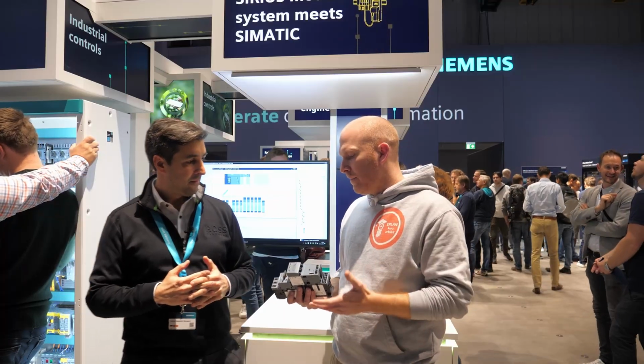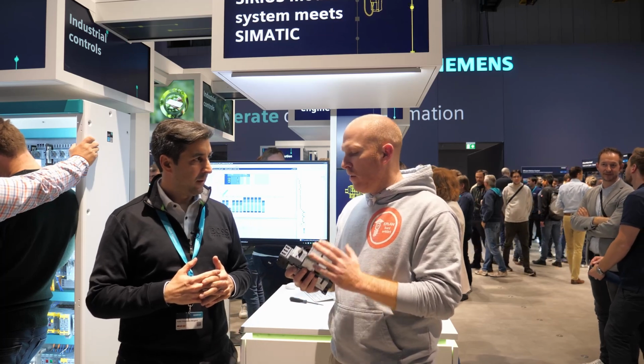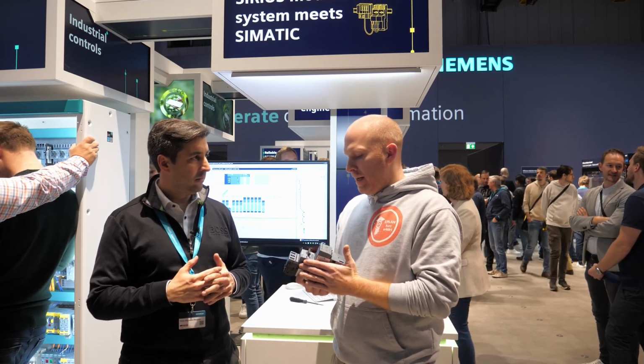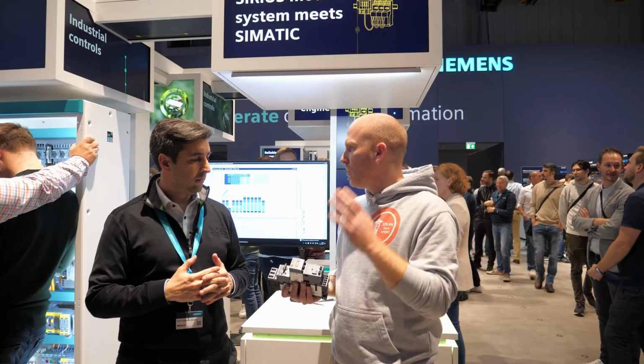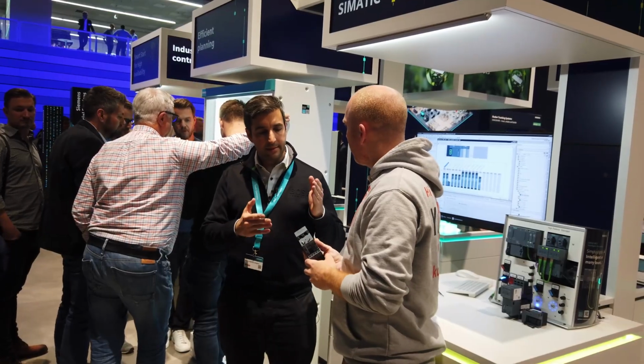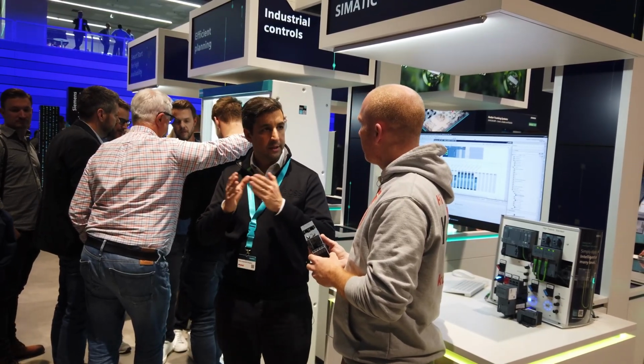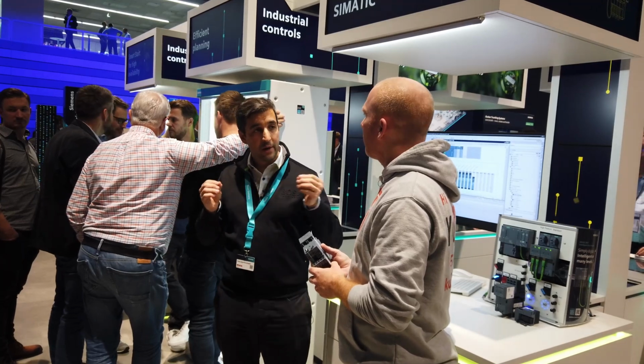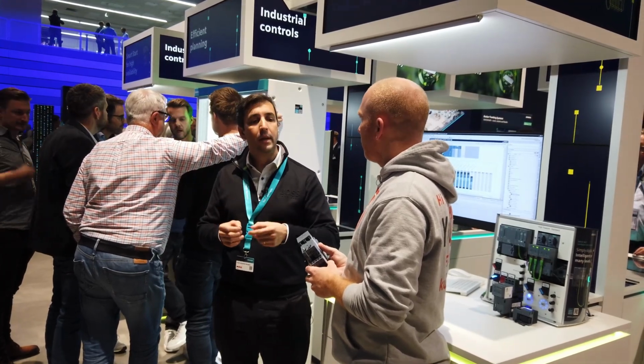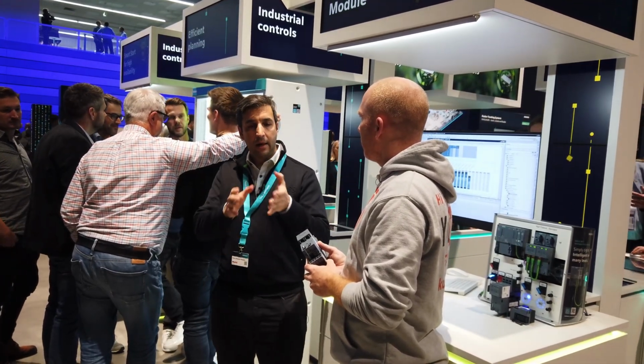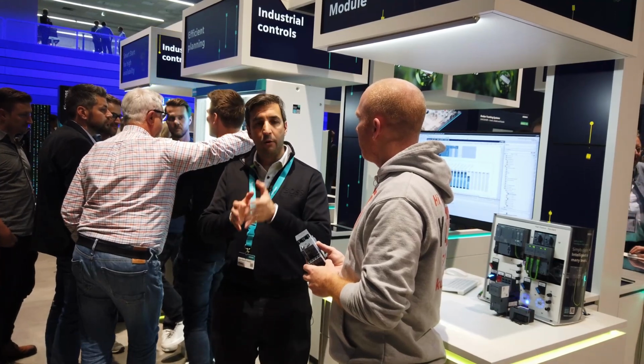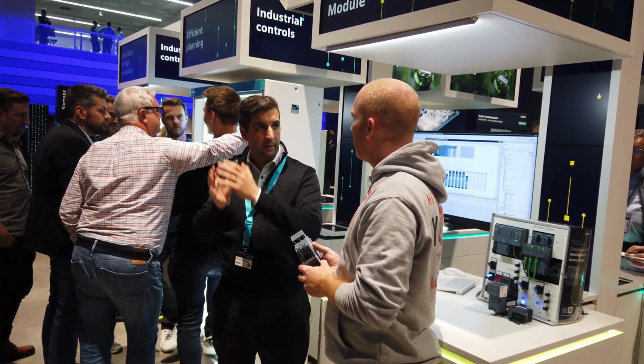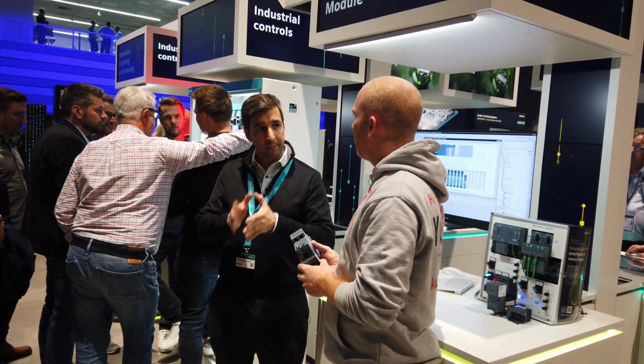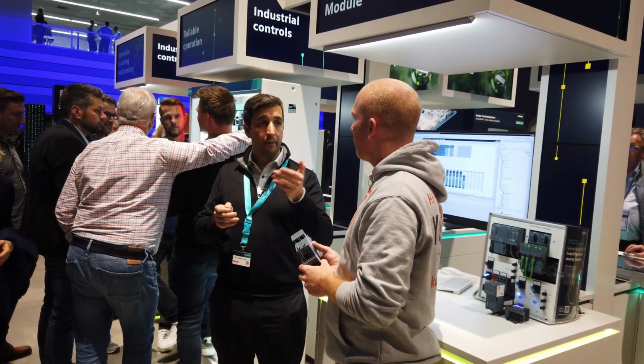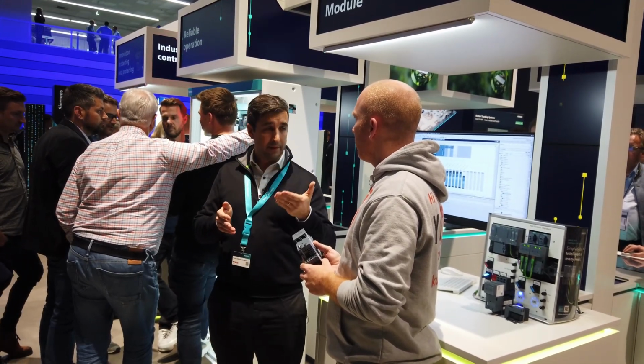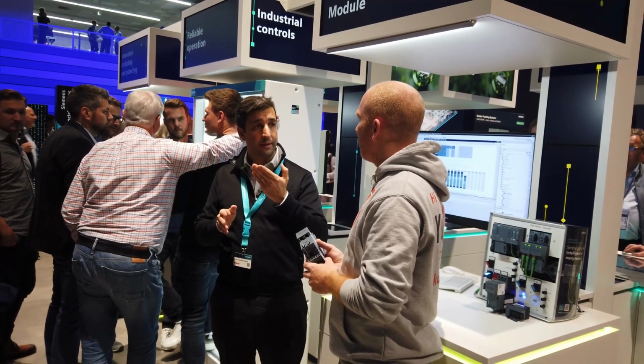Yeah, quite interesting. That means we can get more data out of our normal contactors and MCCBs. How to connect this to the IT world? Well, basically this communication that it has is a rack communication extension rack from the ET200SP communication that you can set up to 16 devices, and from the ET200SP you can go via the PLC to the cloud level, or even you can use the ET200SP multi-field bus that allows you to have parallel communication Profinet and Modbus TCP, and then you can send this information to the cloud.